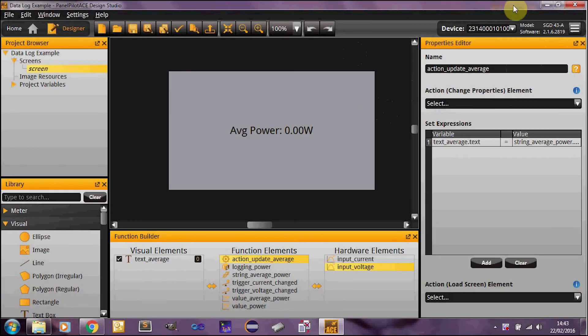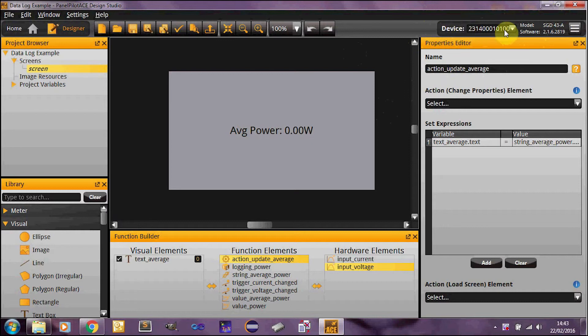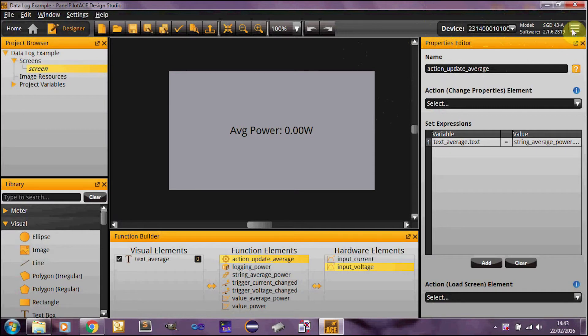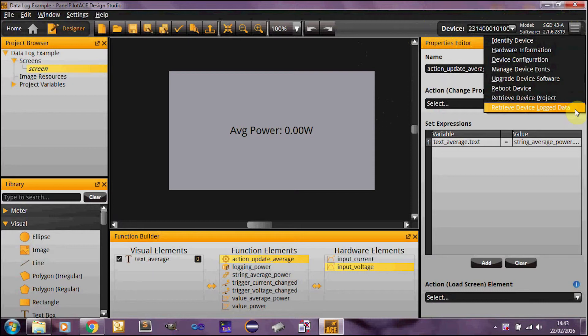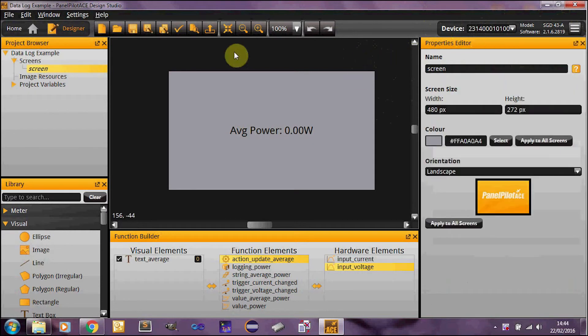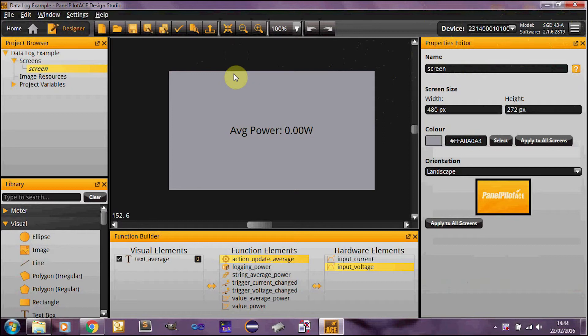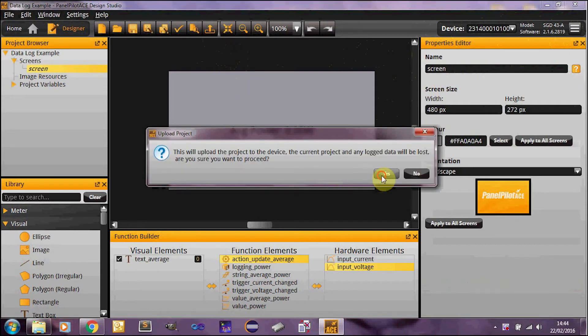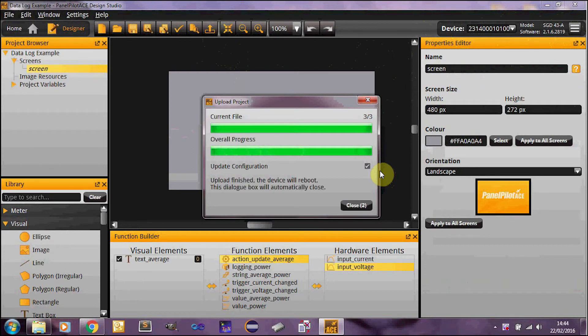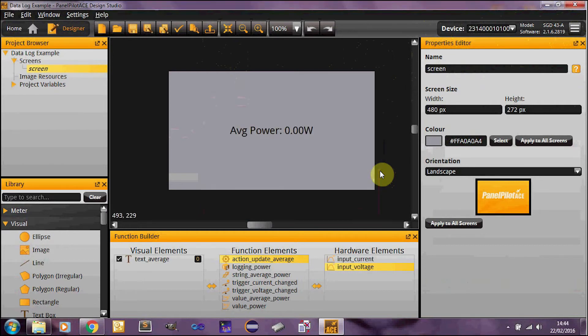So I have now connected one of my SGD 43-A devices to the computer. You can see it connected up here. We've got a serial number, model and software. This button here will give us the options for the device. So for example retrieve device log data, which we'll do as soon as we've uploaded the project. You can do a couple of other things like configure the device etc. But we won't go into that too much for now. So the main thing to notice is that the software version is now 2.1.6.2819, which is latest and greatest at the launching of this video. So it should be able to cope with data logging. So I'm just going to upload the project to the device. There you go. The device is successfully uploaded and rebooted. And it is now displaying an average power of zero. Which is wonderful. So what I'm going to do now is leave this running for a little bit. Accumulate a couple of logs so that we can actually have something to download.